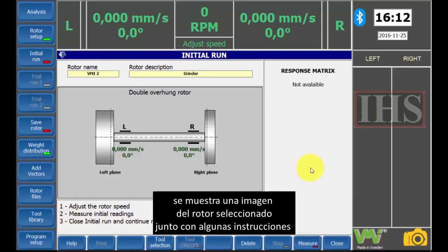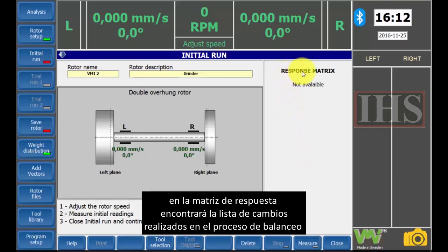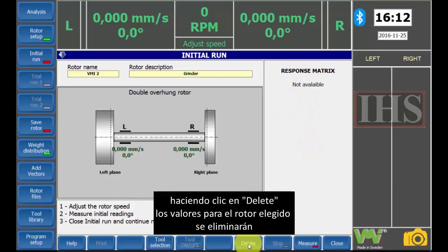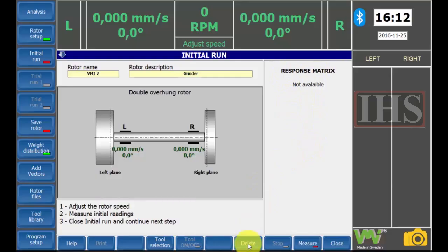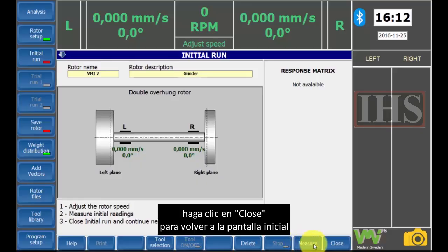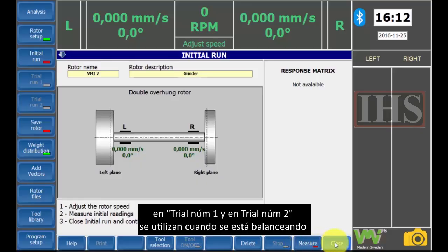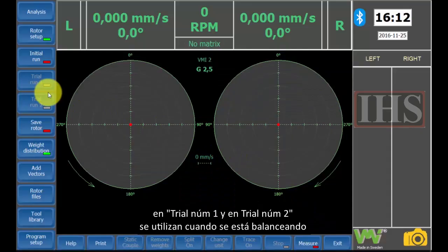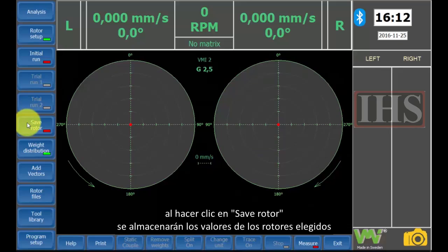On the response matrix, you'll find a list of changes made in the balancing process. By clicking Delete, the values for the chosen rotor are deleted. Click Close to go back to the initial screen. The Trial Run 1 and Trial Run 2 are used when balancing. By clicking Save Rotor, the values of the chosen rotors are stored.